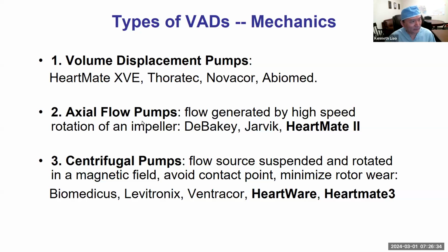That led to the development of the second generation, called the axial flow pump. Some of them have been working very well, especially the HeartMate 2, and the longest support with that pump can be over 10 years. But unfortunately, this type of pump has a higher incidence of pump thrombosis, and it was eventually replaced by the centrifugal pump, what we call the third generation pump. That's the pump we're using now, and the only pump available now is the HeartMate 3, a centrifugal pump that works very well.